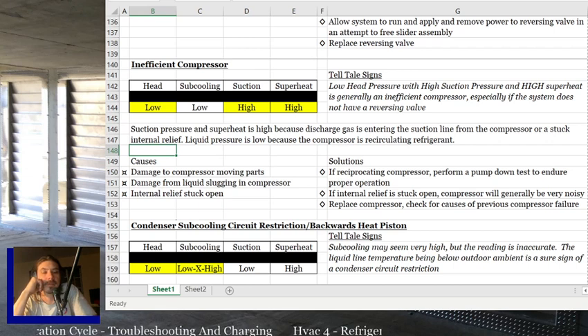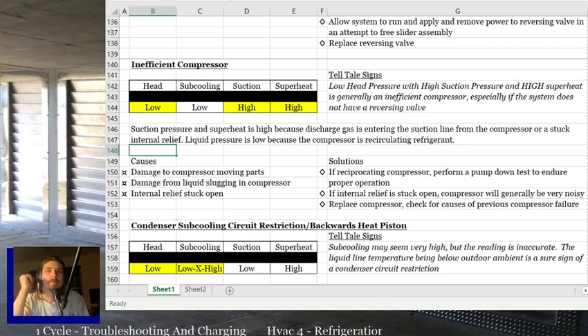So if you've got an inefficient compressor, always look for what happened to the compressor. Anytime you've got problems with the compressor, the first thing you do is figure out whether or not it's worth replacing the compressor. The next thing you do is figure out what happened to the compressor, because you don't want it to happen again. Compressors don't die, they're killed. Alright, so figure out what's going on there.